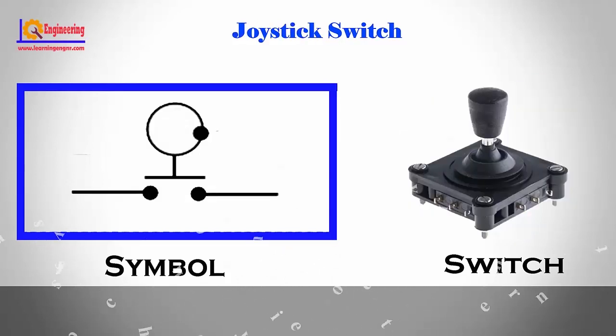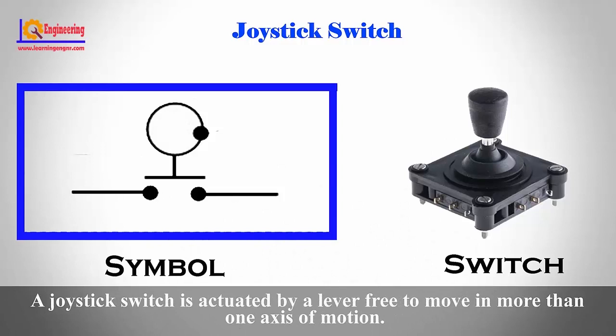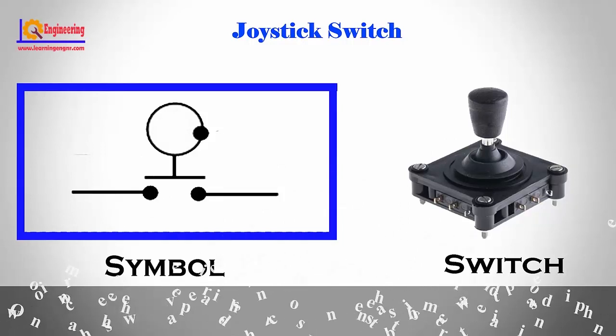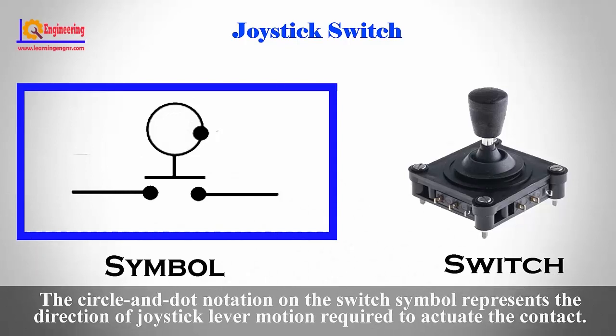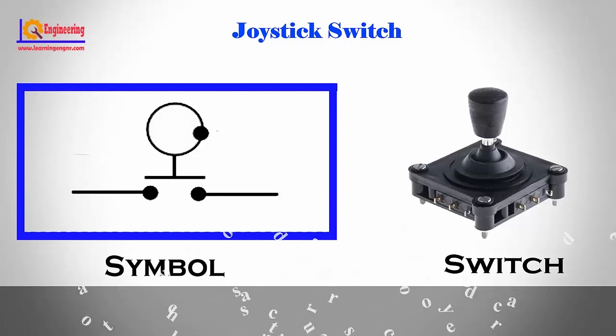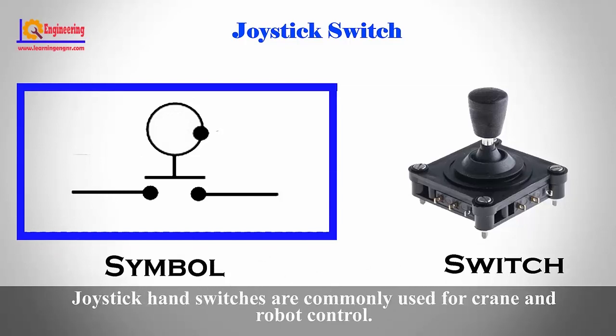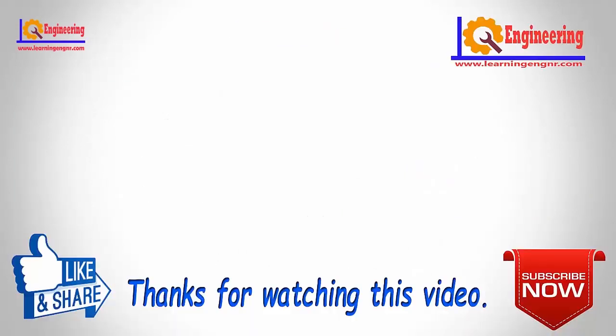Joystick switch. A joystick switch is actuated by a lever free to move in more than one axis of motion. One or more switch contact mechanisms are actuated depending on which way the lever is pushed, and sometimes by how far it is pushed. The circle and dot notation on the switch symbol represents the direction of joystick lever motion required to actuate the contact. Joystick hand switches are commonly used for crane and robot control.